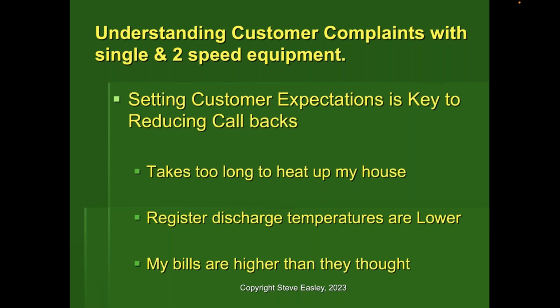Secondly, as we talked about earlier, the register discharge temperatures are lower, so people would say, wait a minute, it feels like cold air coming out of the system. And in some cases, if their electric utility bills are high and they're running on peak load, during peak periods, their bills were higher than they thought.